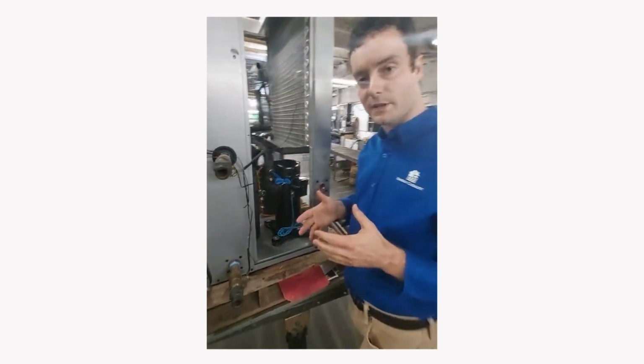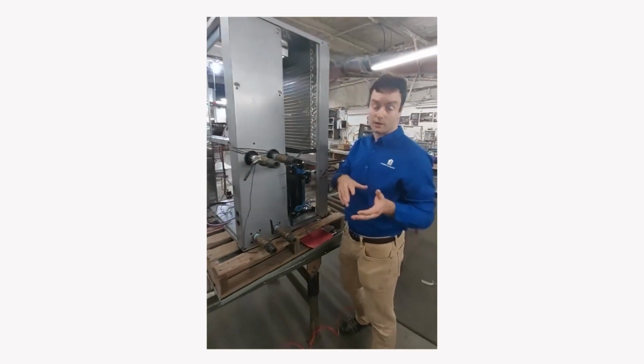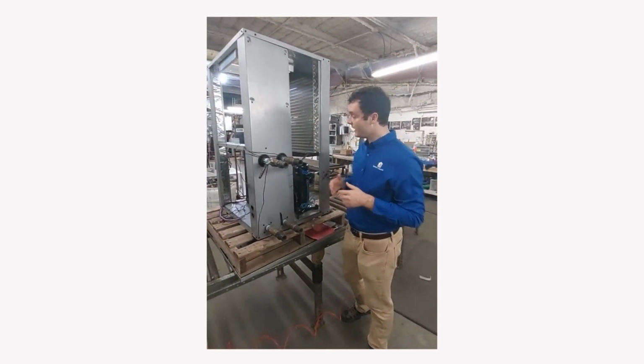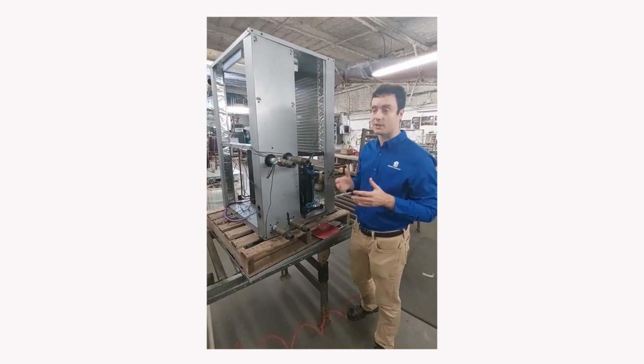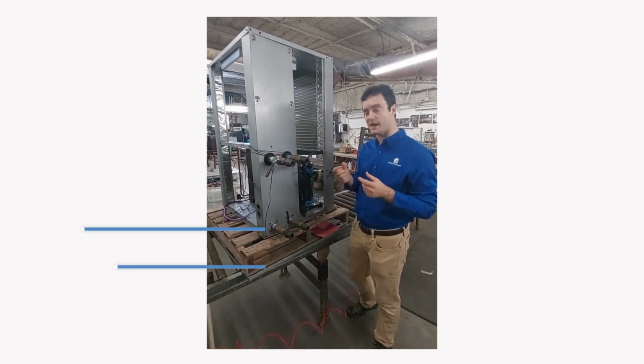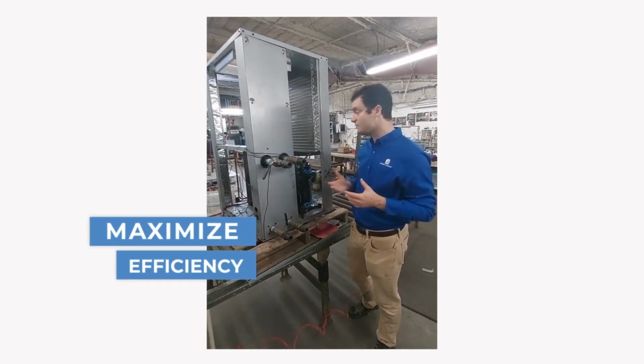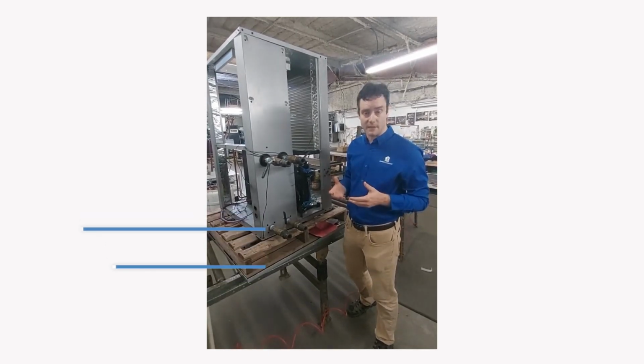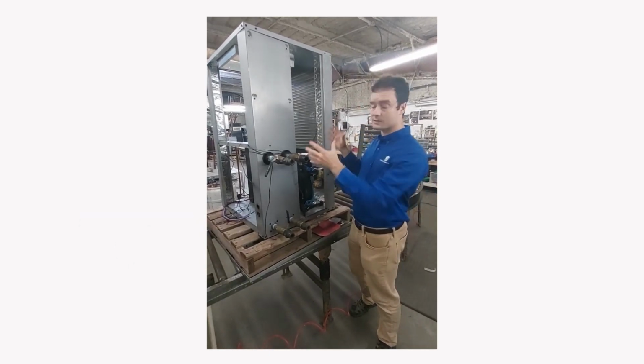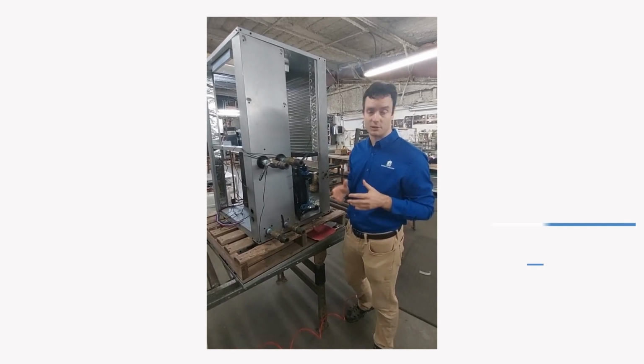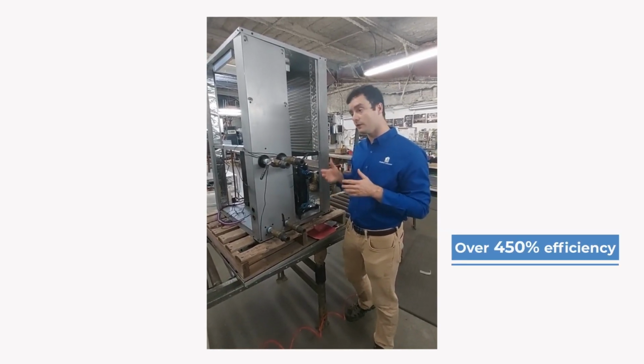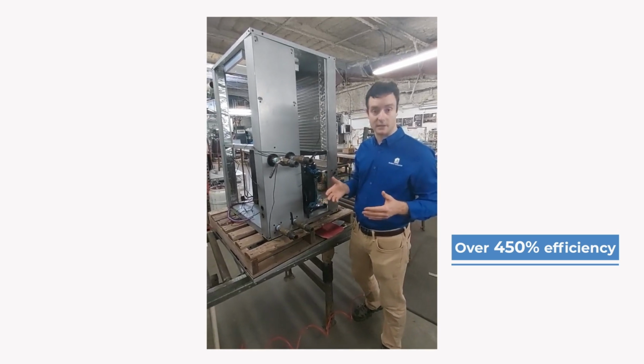We use braze plates on all of our units, both for our evaporator and our condenser. And we use pretty large braze plates, so that we maximize the efficiency. In fact, that is one of the many ways that we've designed this heat pump to be one of the most efficient, if not the most efficient, heat pump in North America for heating a home with an existing hot water system.